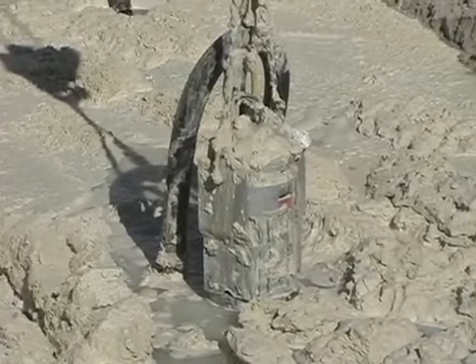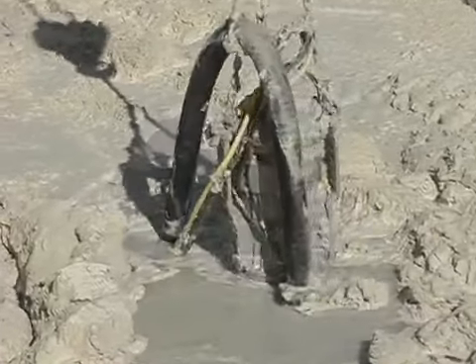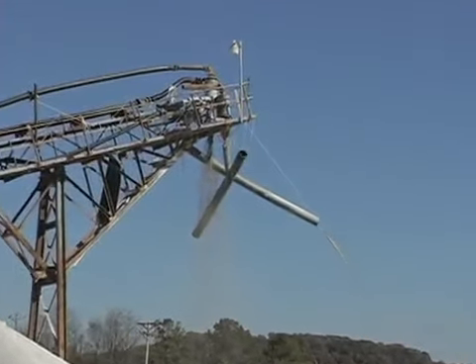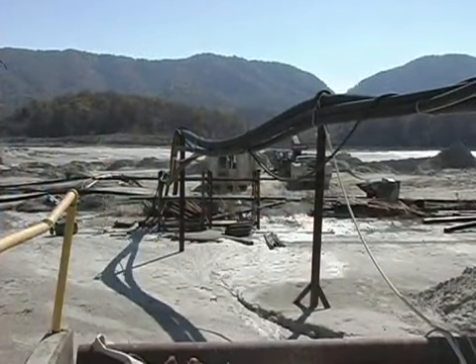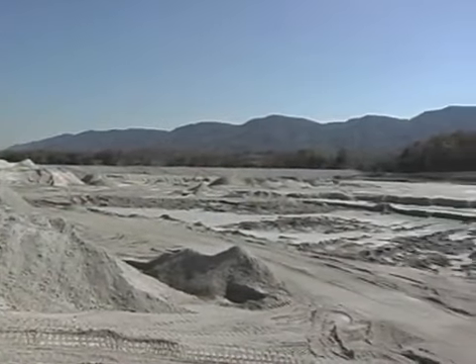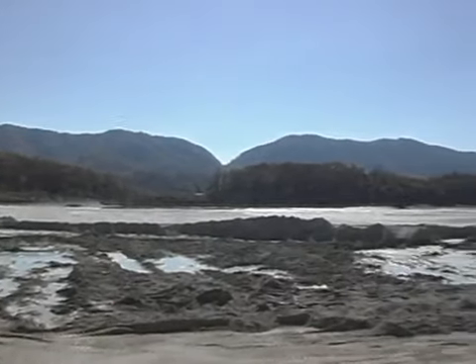This pump has been operating at 500 gallons per minute, 25 to 30 percent solids, five days a week, nine hours a day, producing approximately 400 tons of sand a day. The sand is pumped through approximately 300 feet of four-inch polypipe, with about 18 feet of static lift from a 1,400 by 600 foot sand-filled pond that is 30 to 70 feet deep.